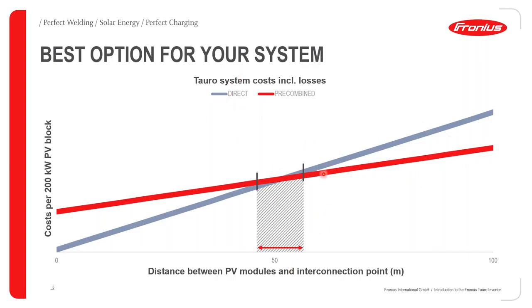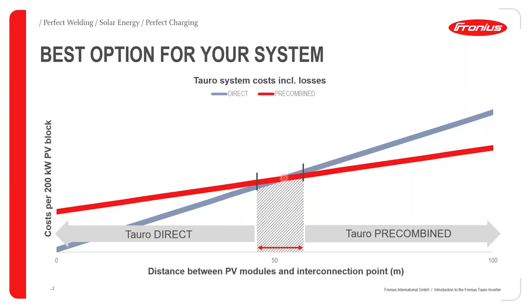Therefore, at this intersection point going forward, the pre-combined inverter version makes a lot more sense for your design case. So anytime you are considering the Tauro versions of the commercial Fronius inverters, and the distance from the inverter to the point of interconnection or the transformer is less than 50 meters, we would recommend that you go for the direct version of the Tauro inverter. When that distance exceeds 50 meters, we would recommend the pre-combined version of the Tauro. This is important to note, because when you are doing your orders, you have to specify which Tauro version you would like to purchase, whether the direct or the pre-combined version.